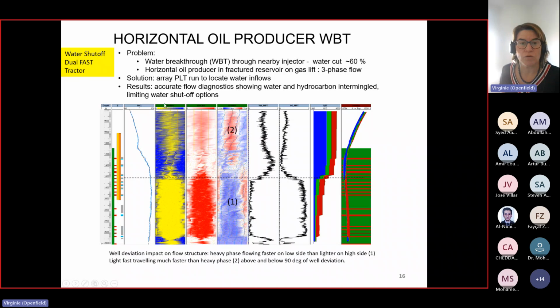Inclination here. Water holdup E is water holdup from the conductivity probes. So here, all these three maps: water holdup, gas holdup in red and white, spinner in red and blue. The convention is that the middle is the high side. So the high side is in the middle, so it means that you have a light phase here with zero water holdup. It can be gas or oil. So the yellow stands for hydrocarbons. It's on the high side.